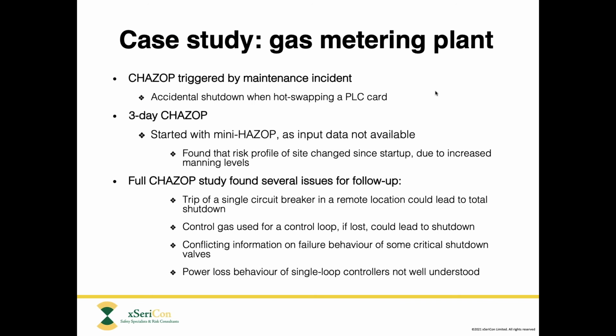And to me, that was really the value of this whole CHAZOP study. It paid for the CHAZOP study many times over, just finding that one result, because clearly that was the major potential source of loss of availability for their plant. So that was the main recommendation coming out of this study, to address that and to try to deal with the lack of redundancy in that particular power supply.